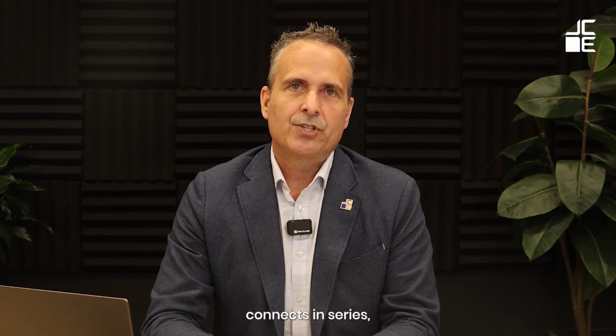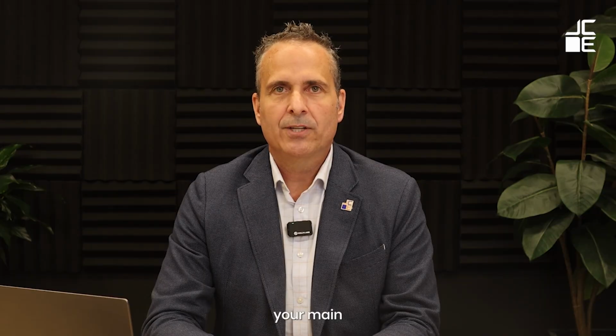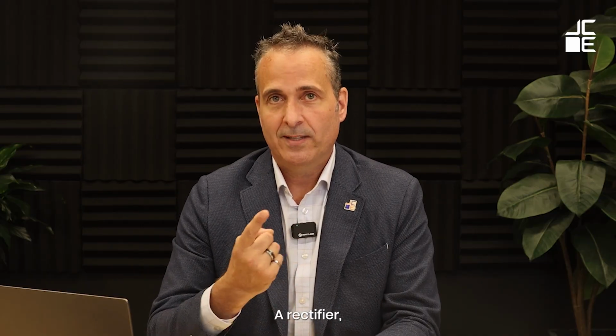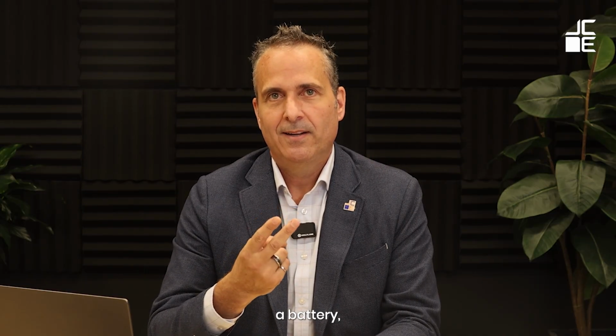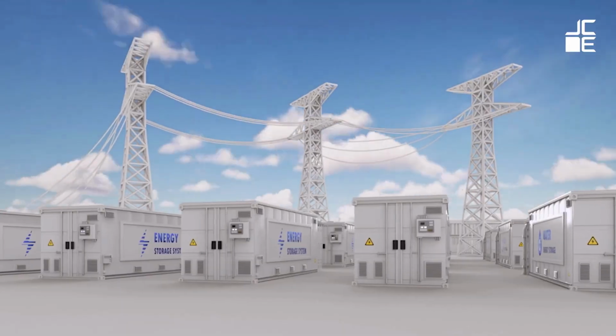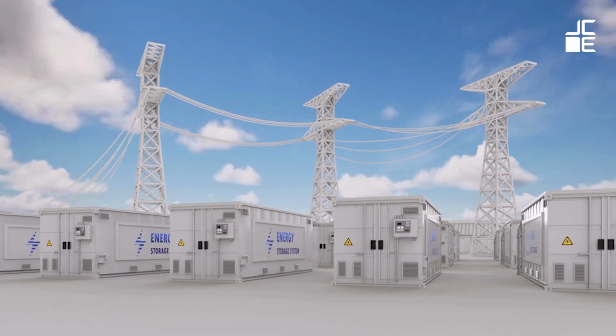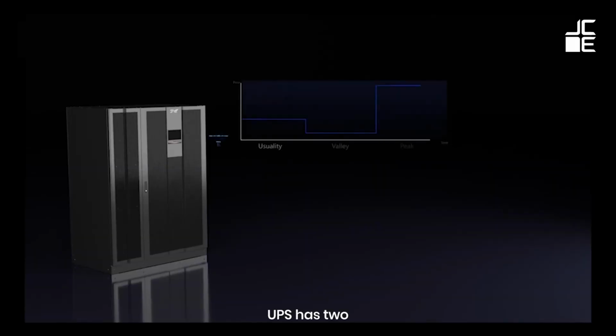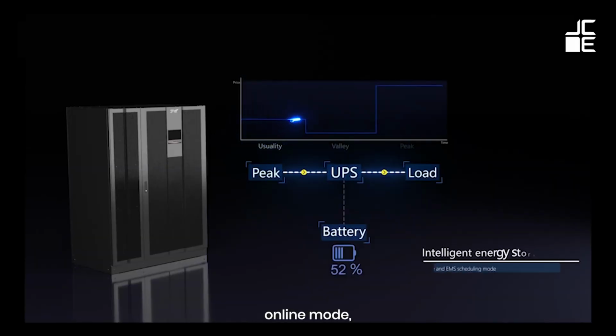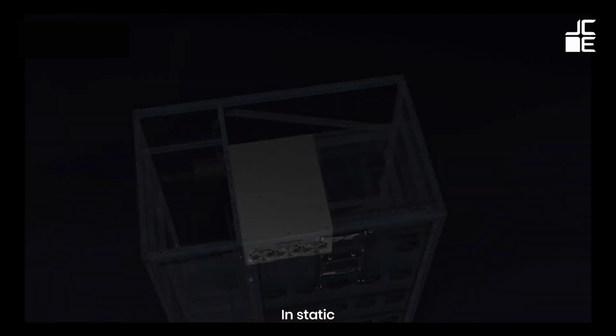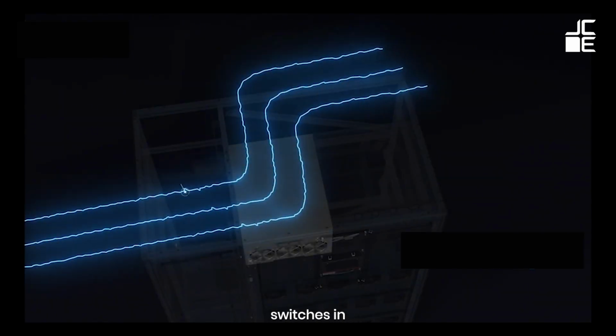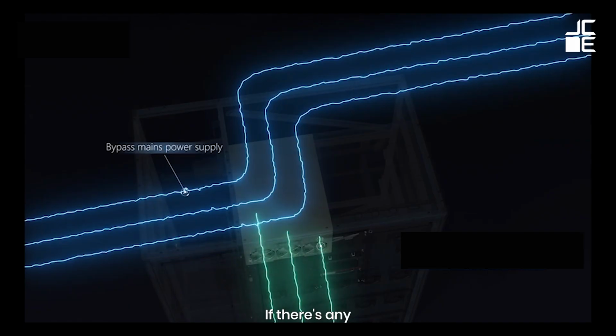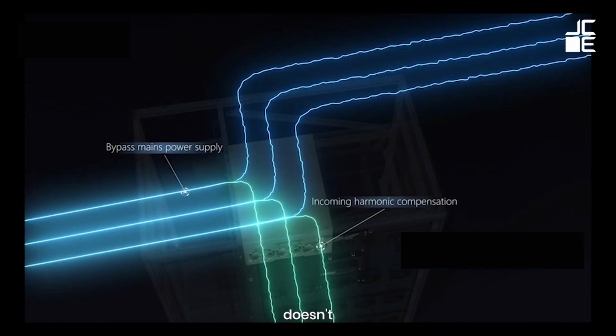The system connects in series just after your main transformer. It's built from three components: a rectifier, a battery, and an inverter. UPS has two operating modes. In true online mode, all incoming utility power is rectified and inverted, ensuring your loads see a perfectly clean, stable waveform. In static bypass mode, the system switches in just 2 milliseconds if there's any grid interruption, so fast that your equipment doesn't even notice.